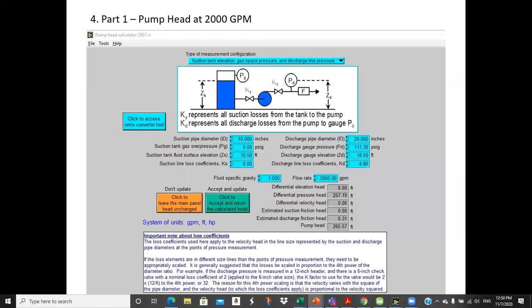So there's a little note down here, and what it says is that if the fittings are of a different diameter than the point of pressure measurement, you have to adjust the K values. And so you take the ratio of the diameters. It does a little example here where the pressure measurement is a 12-inch versus a 6. Well, we're a 20 versus a 10. The ratio is the same. You take it to the fourth power, which is 16, and then you multiply it by what you looked up for your K values, which is 0.1 plus 0.2 is 0.3. So 0.3 times 16 is 4.8.